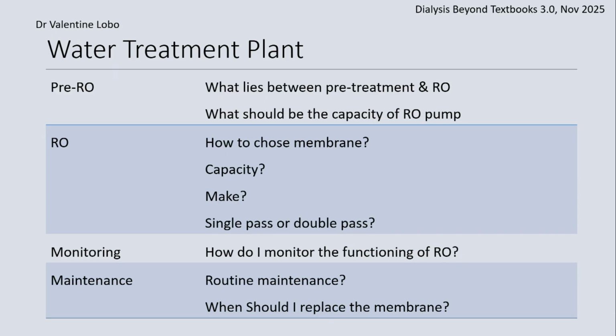So the capacity of the RO pump, it's a centrifugal stainless steel pump. It should be capable of developing pressure of up to 15 kg per centimeter squared. For optimum RO performance, membranes usually require about 10 kg per square centimeter for optimal operation. If you cannot deliver that, then you're not going to achieve that 90% TDS reduction from the incoming stream of water. So one would need an RO pump that would develop at least 15 kg so that it would go beyond. Most stainless steel housings are limited to a breaking strength of 15, so you don't want to go beyond that pressure additionally.